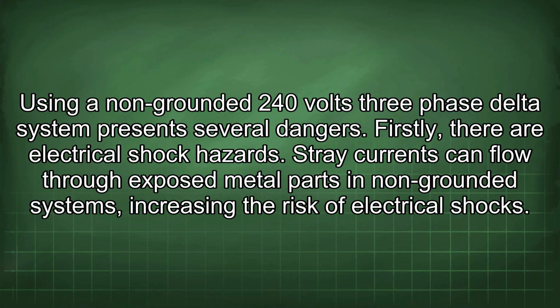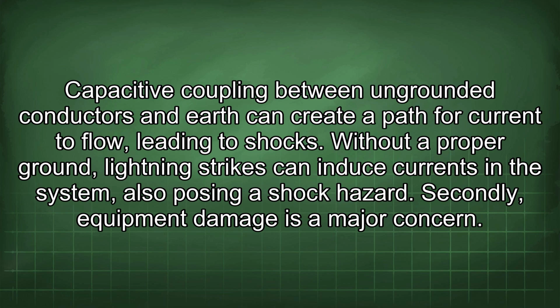Using an ungrounded 240 volts three-phase delta system presents several dangers. Firstly, there are electrical shock hazards. Stray currents can flow through exposed metal parts in ungrounded systems, increasing the risk of electrical shocks. Capacitive coupling between ungrounded conductors and earth can create a path for current to flow, leading to shocks. Without a proper ground, lightning strikes can induce currents in the system, also posing a shock hazard.